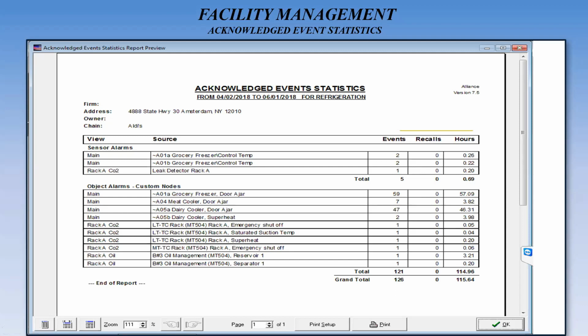So, if somebody from one of your stores calls and says their freezer and cooler can never keep the temperature where it needs to be, you pull this report and see: freezer door ajar, 59 alarms for 57 hours; dairy cooler door ajar 47 times for 46 hours. It's quite possible that's what's causing the temperature problem—when they stack product into the freezer or cooler, they prop the door open with a U-boat cart, and to make it easy they just leave the door open for 10, 15, 20, 30, 45 minutes at a time. That causes the temperature to drift up and triggers an alarm.